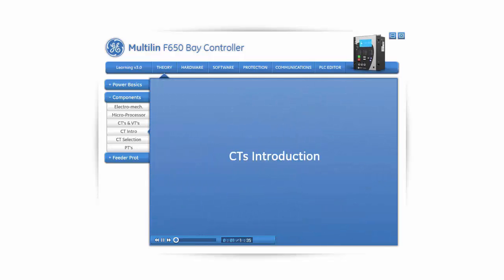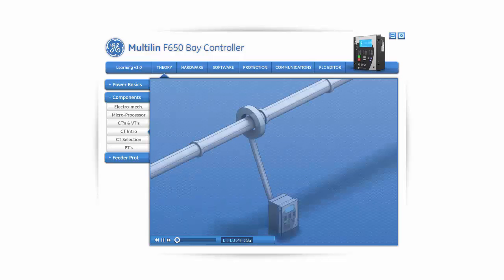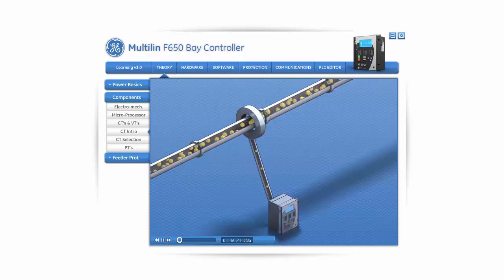CTs Introduction. The function of a current transformer, or CT, is to take a current flowing through a wire or cable and step it down to a magnitude that a protective relay can measure. A primary characteristic of CTs is their conversion ratio. In this example, our conversion ratio is 100:5, meaning that if 100 amps are passed through the primary phase wire, the CT will scale this down to 5 amps and direct it to the relay via the secondary windings.